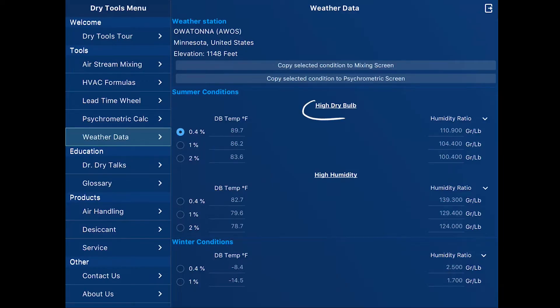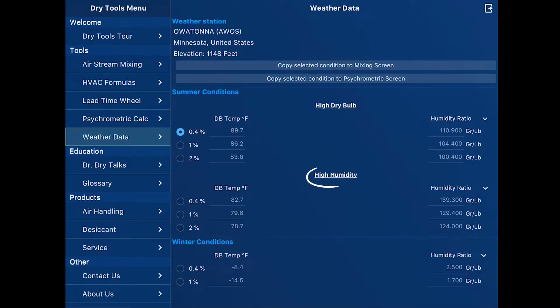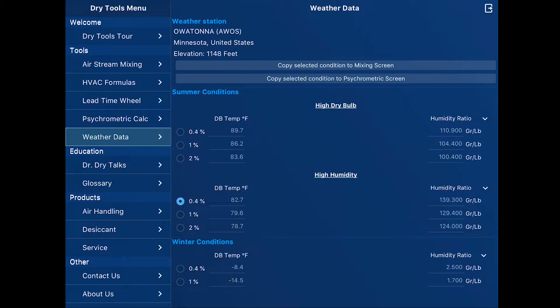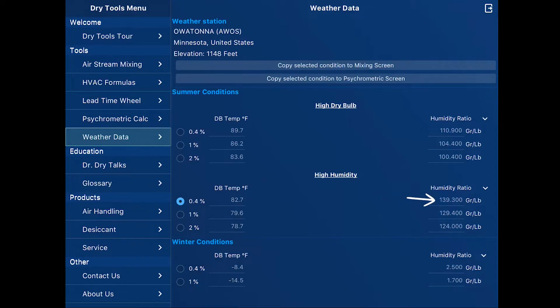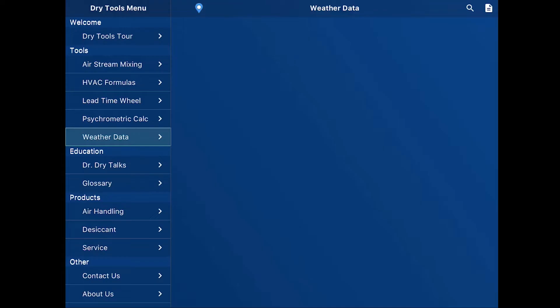In the middle of the page, the high dry bulb conditions. In the center of the page, high humidity conditions. I'm going to go ahead and select the 0.4% conditions. You'll see that's 139.3 grains. So that's sunny southern Minnesota weather conditions.